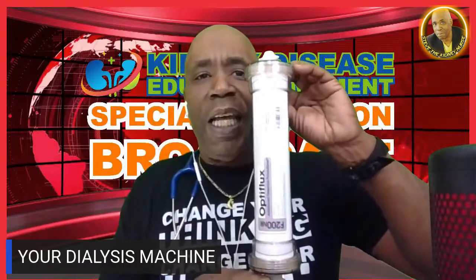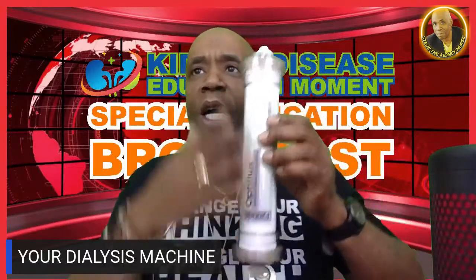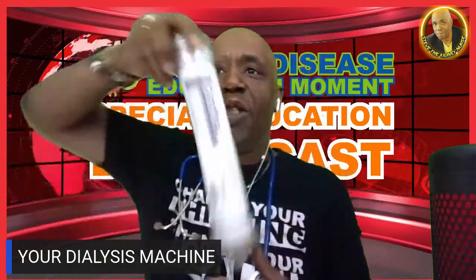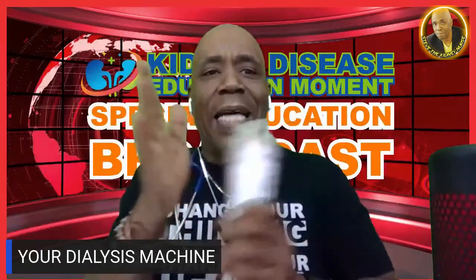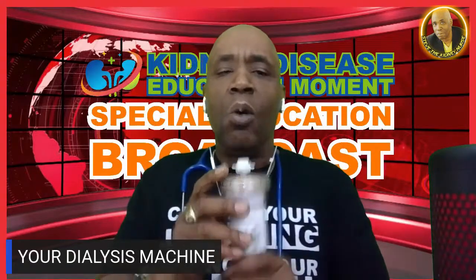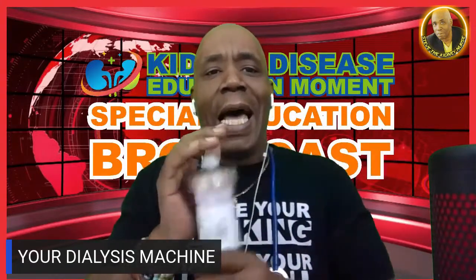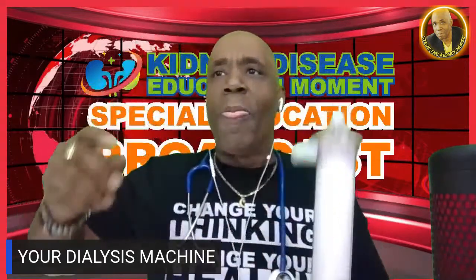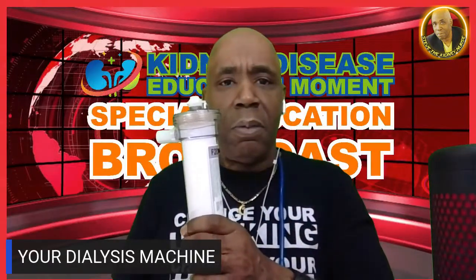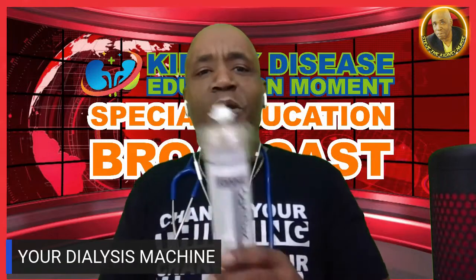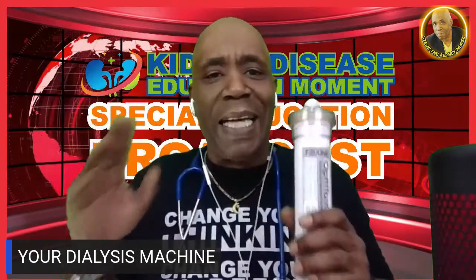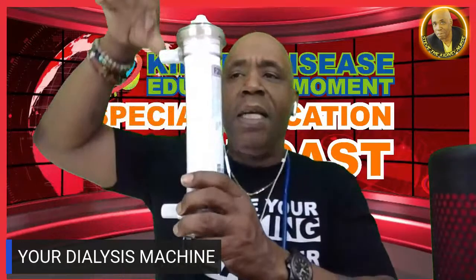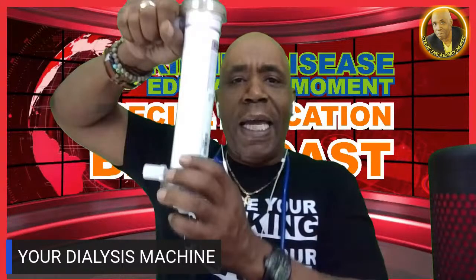If you go into your clinic and you see this dialyzer upside down, ask the technician, can they turn it upside up? The venous side is only up when we prime in the dialyzer, getting the air out. Once we finish priming the dialyzer, we turn it with the red side up. You saw it on the hoses. The red up, blue at the bottom. When you go to treatment, make sure that's how your connection is on the machine. Red here, blue at the bottom. Not the other way around.